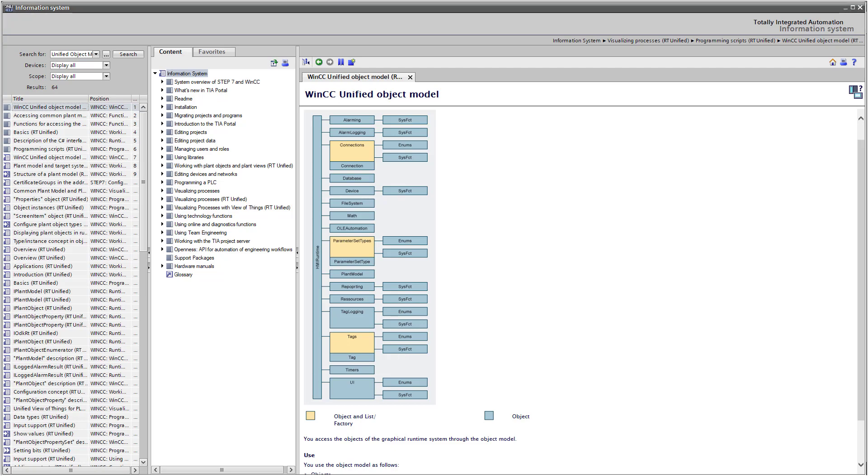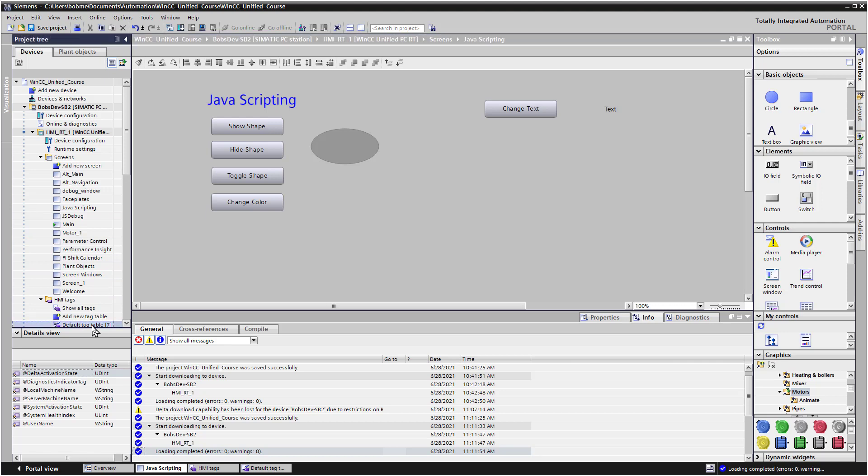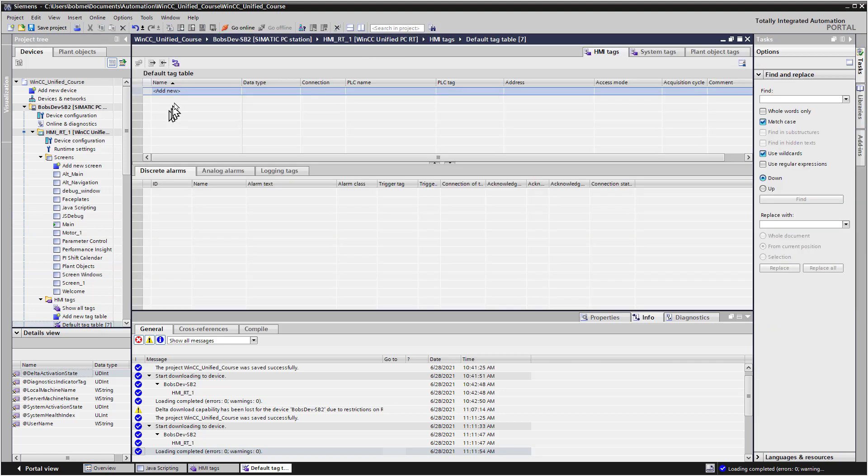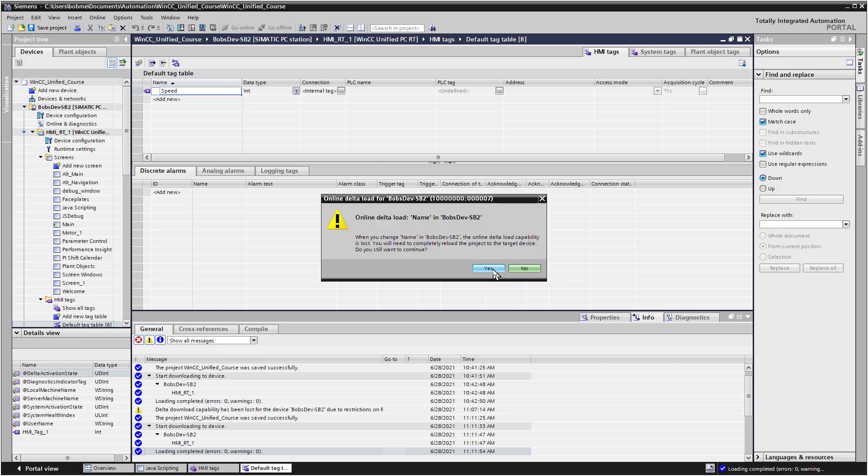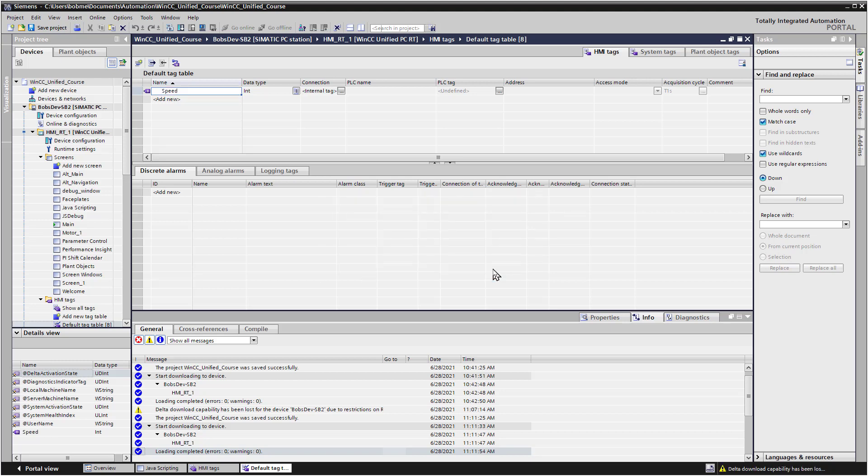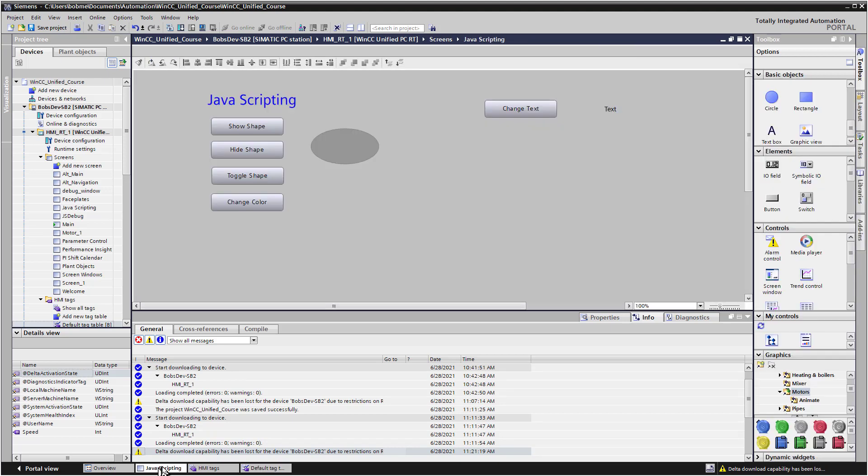So going back to the engineering software, let's go to our tag table. And we're going to create a tag. And let's just call it speed. So I'll double click add new. And the online delta load warning will come up, meaning we'll have to do a full compile now. That's OK. We'll just choose yes. And it's just an internal tag connection.